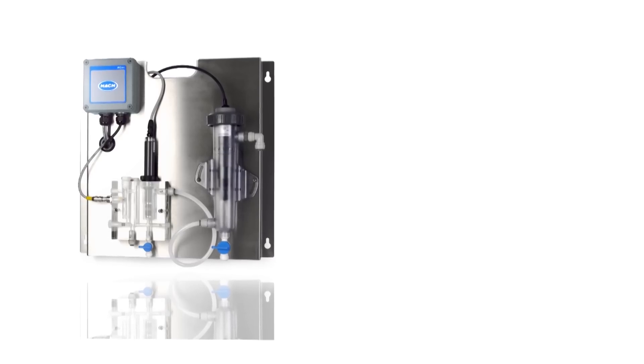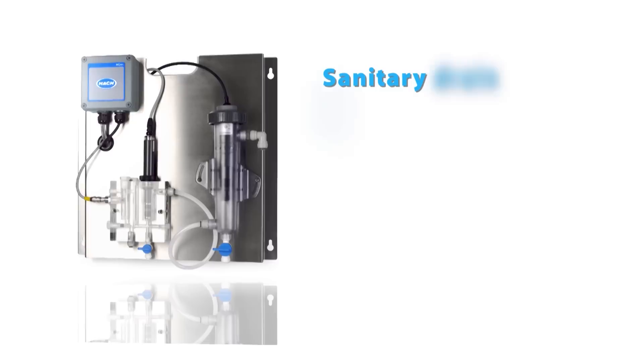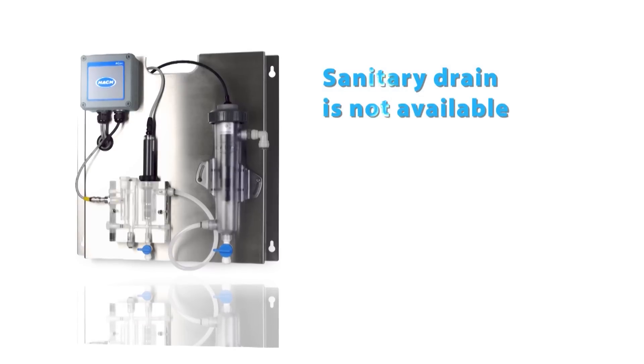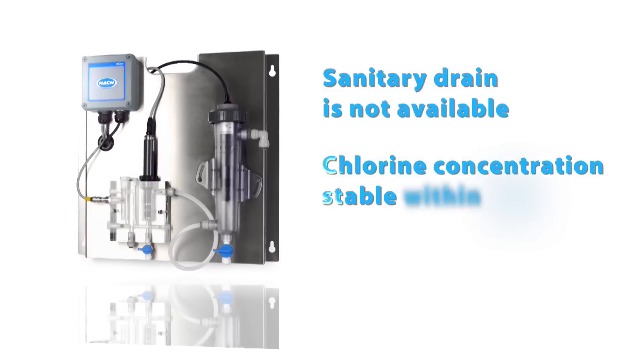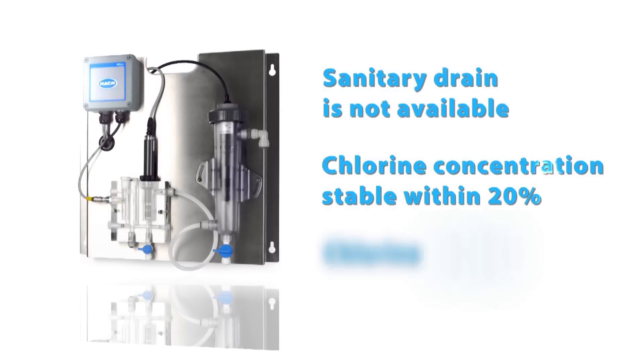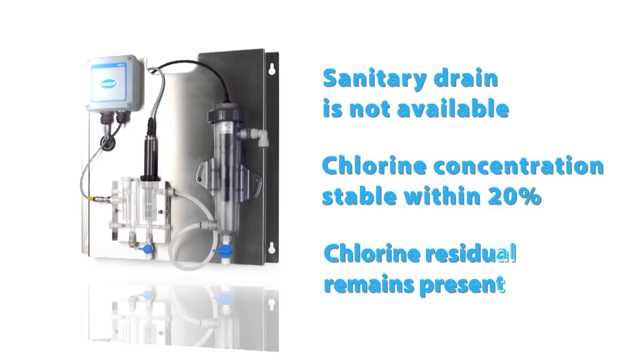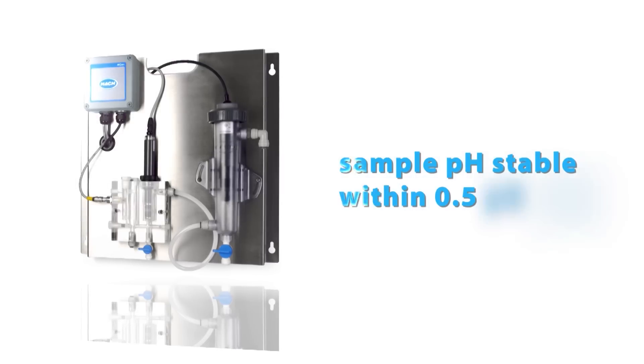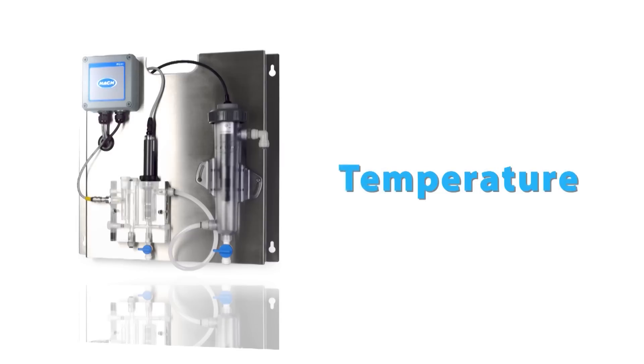The HACH CL10 is a great choice for applications where a sanitary drain is not available, the chlorine concentration is stable within 20%, and the chlorine residual remains present. The pH also needs to be stable within 0.5 pH units, and flow, pressure, and temperature shouldn't fluctuate outside of the typical seasonal variation.